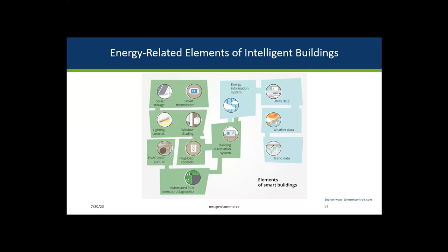The building systems feed data into the fault detection and diagnostics that can detect and anticipate any system malfunctions, possibly even generating and distributing appropriate service tickets. Weather data, utility grid data, and trend data on the right of the image are also used to inform how the building should operate and to facilitate the powerful feedback loop that we noted earlier.